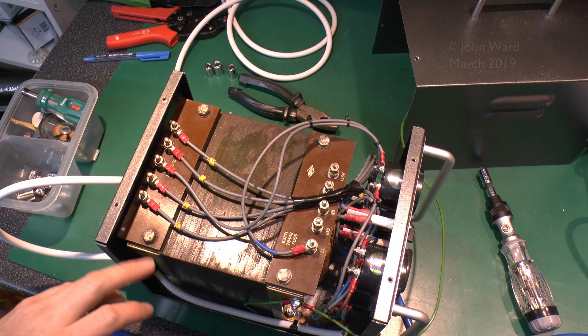So that's the wiring inside complete. We've got the neutral connected here, mate L1 there, and the other wire is the supply, so we put that in where it's marked 230. Then we have the four outputs marked 1, 2, 3 and 4. Two of them give us a lower voltage, and two a higher one - basically 200, 215, 245 and 260 - and those are controlled by the switch on the front panel. I'll also put a fixing here.